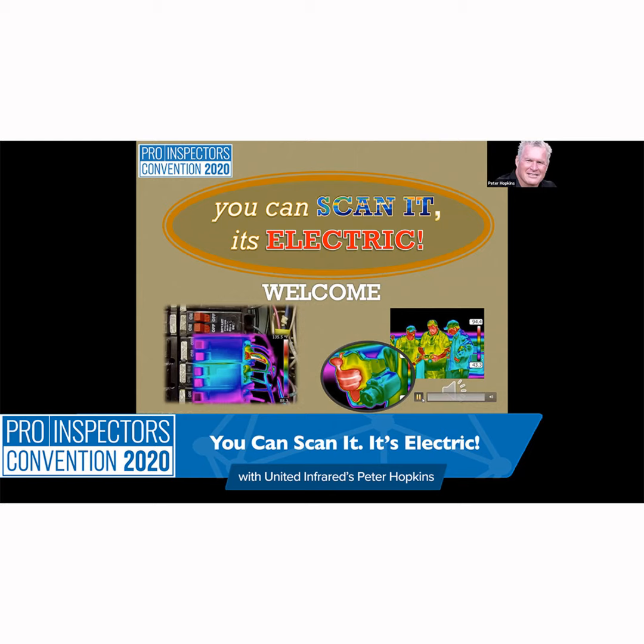I'm giving you an example - this is a university located in the San Diego area that we were helping with IR windows. We're basically showing where their switchgear is. We're going to put in 1 or 2 windows in this panel, and they use what's called a Greenlee, which is a press. They'll take this metal cover off during a maintenance window, then press a hole into that metal and install this window.